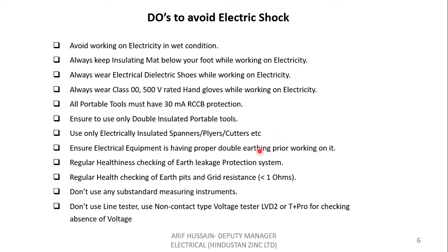We should have regular health checking of the earth leakage protection system, so that in case of earth leakage or fault, it will trip and protect the human body. We should have regular health checking of earth pits and maintain a grid resistance of less than 1 ohm, so that fault current passes through the earth rather than through the human body. We should not use any substandard measuring equipment or line testers — we should use only non-contact type voltage testers like the LVD2 or the T+Pro.